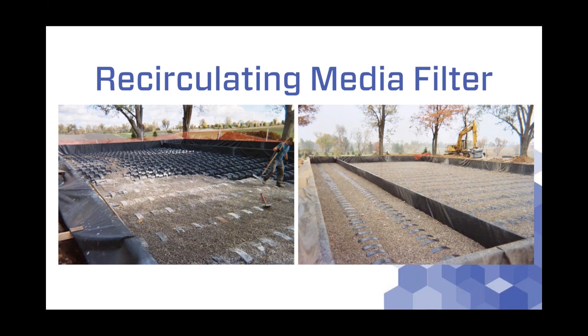Distribution laterals are put over top of the treatment medium after it's placed. When we dose — for example, 100 gallons to the entire system — on the 80% side, 80 gallons will be returned through the underdrain system back to the recirculation pump tanks and re-dosed out into the system numerous times per day, so the effluent is of higher quality. The 20% side — 20 gallons of that 100-gallon dose — goes out to final dispersal, in this case the drip irrigation system. That's how we make a quick, easy split of the effluent for our recirculation rates.